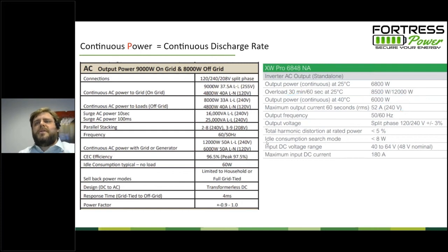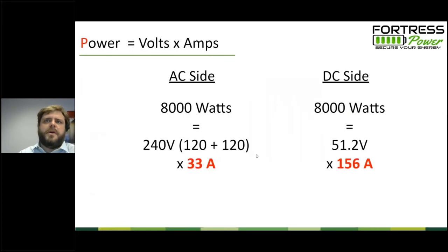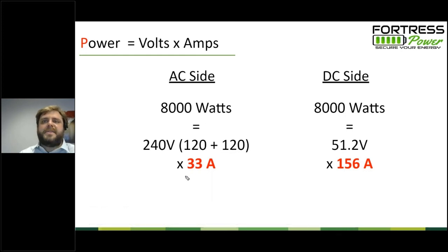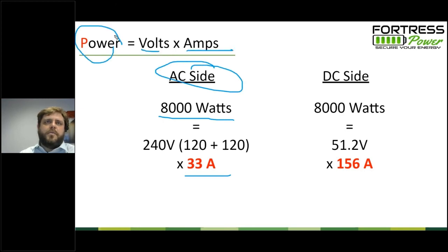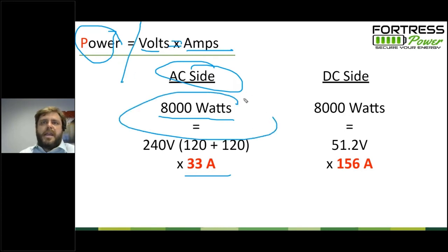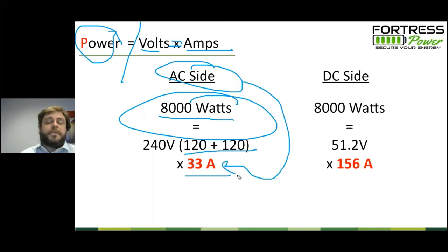So continuous power, the continuous discharge rate, is a little bit of an easier one. The biggest gotcha is that you look at the AC output of the inverter and it's 30 amps, and you think, oh okay, that's pretty low. If you take 8,000 watts and divide by the AC side voltage, and a volt times an amp is a watt, so if you take your wattage and divide out your voltage, you'll get your amperage. So 8 kilowatts on a 240 volt system is 33 amps.